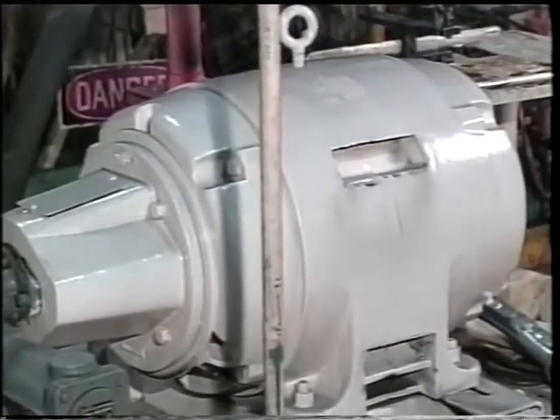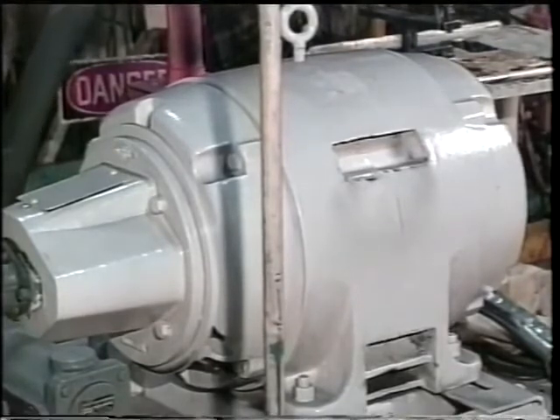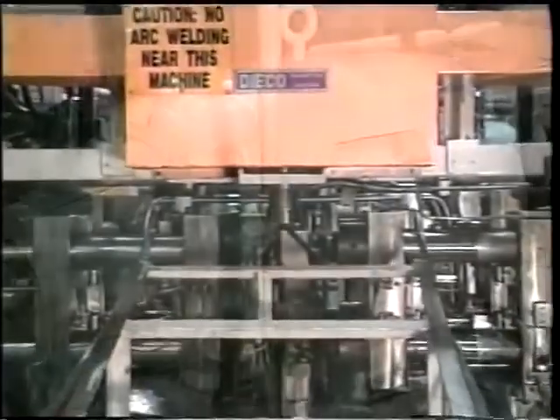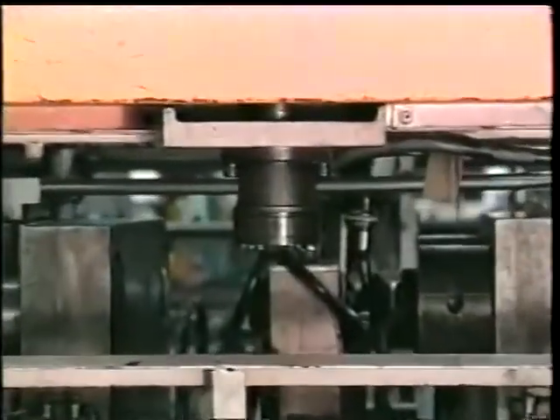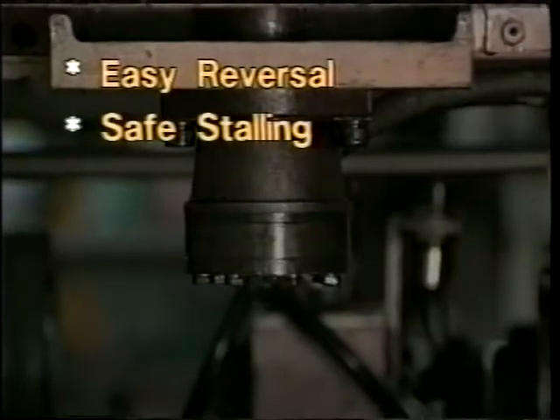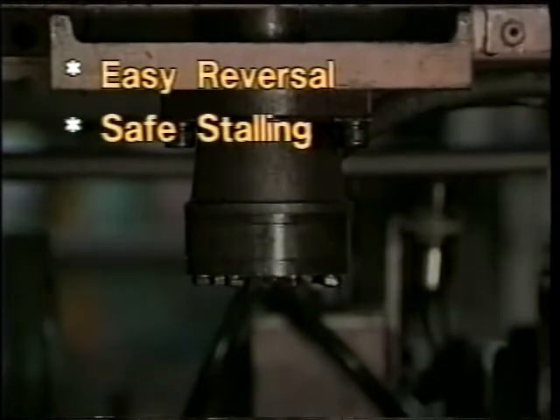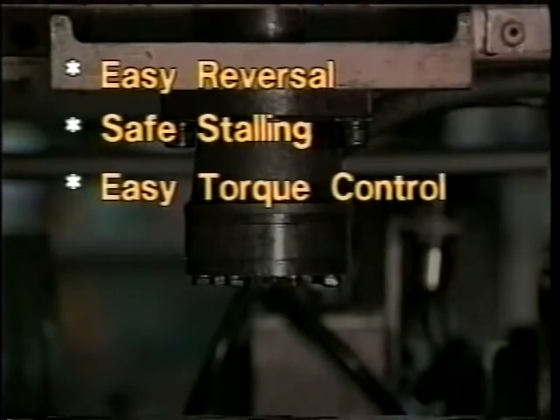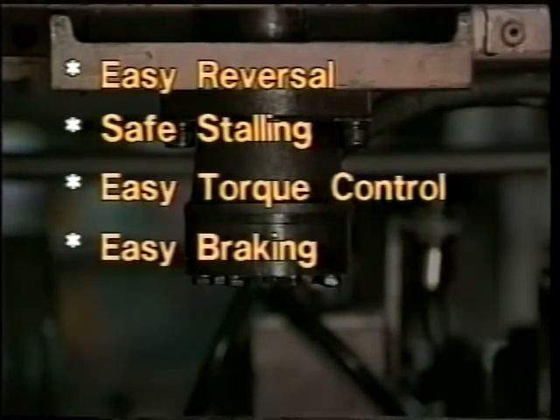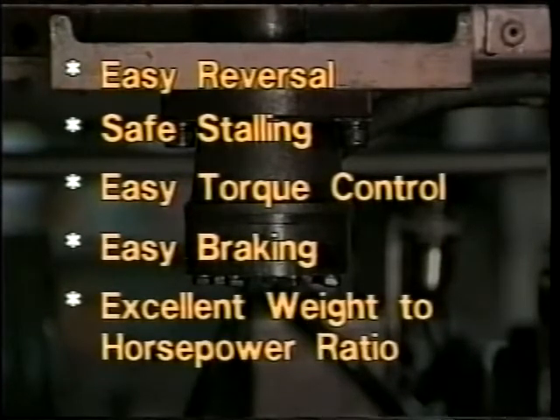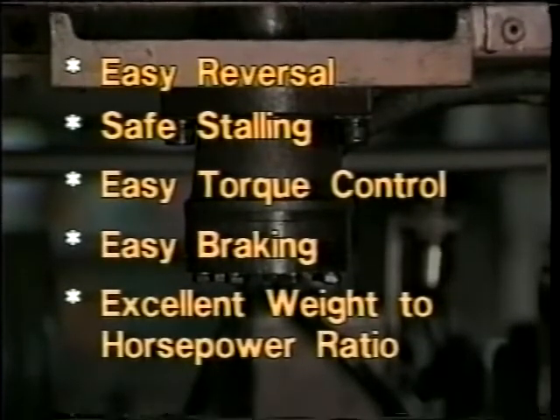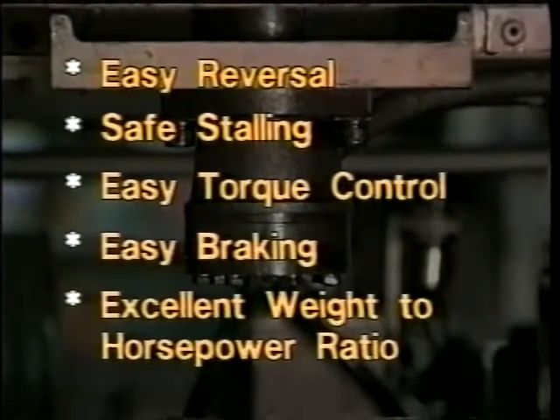In most industrial systems, the prime mover of hydraulic motors is usually an electric motor. In many applications, an electric motor could perform the same function, yet hydraulic motors continue to be widely used because of certain advantages. These include easy reversal of rotation direction, an ability to stall without damage for extended periods, easy torque control throughout the range of operating speed, easy dynamic braking, and a weight-to-horsepower ratio that greatly favors hydraulics. Typically, a 100 horsepower hydraulic motor will weigh about 50 pounds, while a 100 horsepower electric motor can weigh half a ton.